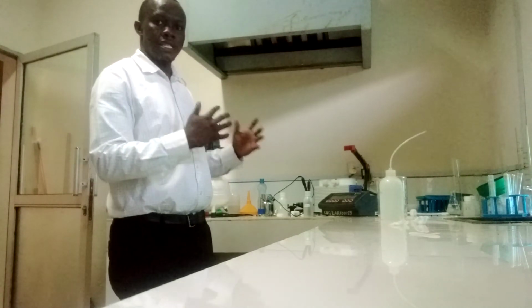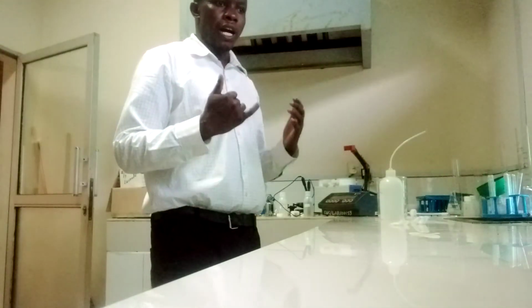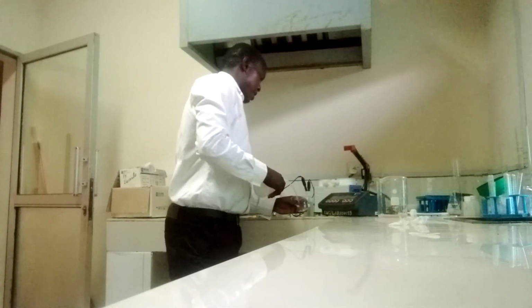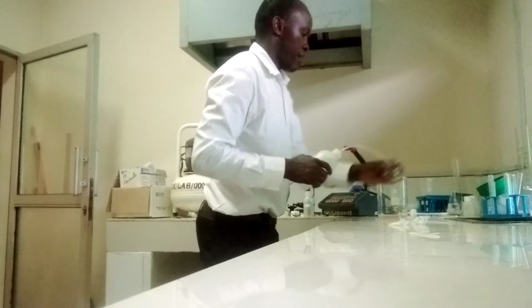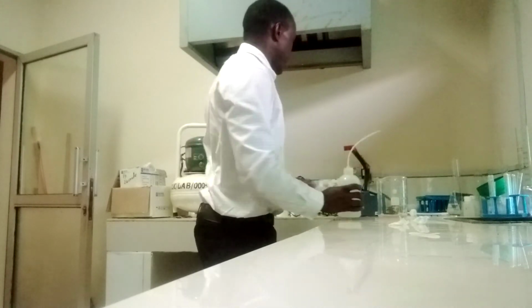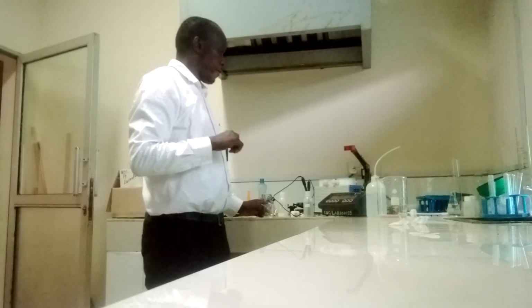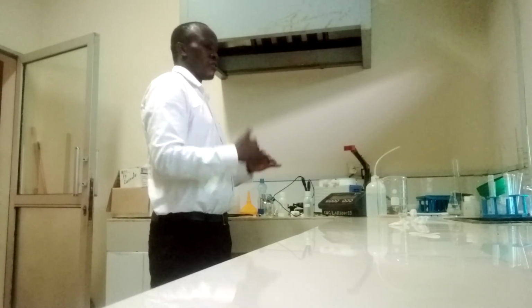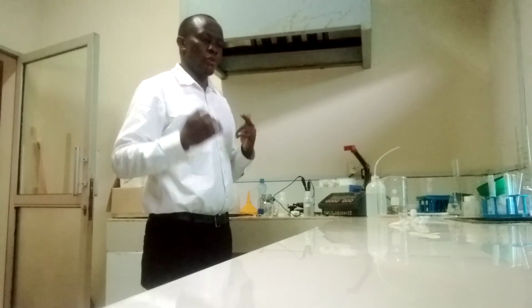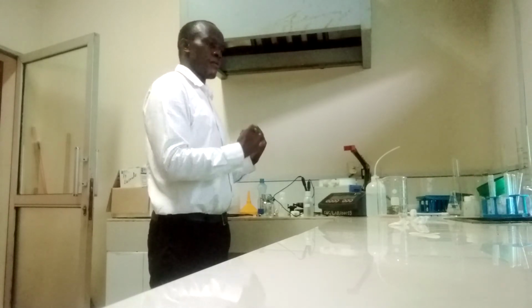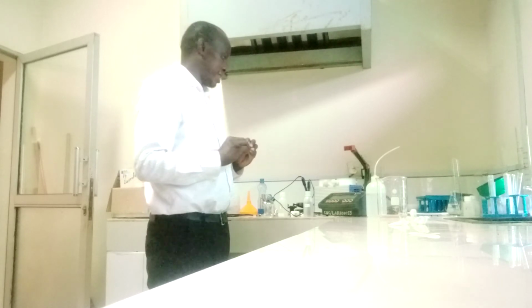As it does that, you wait until it has attained the pH, or it has measured the pH of that particular sample. Then you confirm. When you confirm, it goes back to the reading mode where it now measures the pH of that particular buffer as a solution. And with that, now you are ready. You can now use the pH meter for pH measurements after you have calibrated.